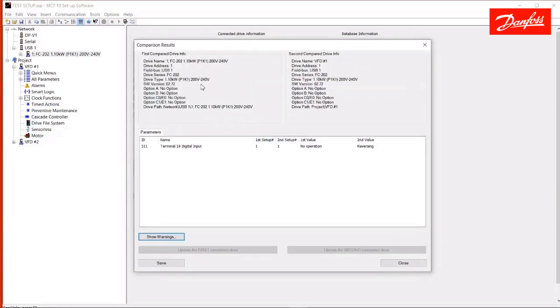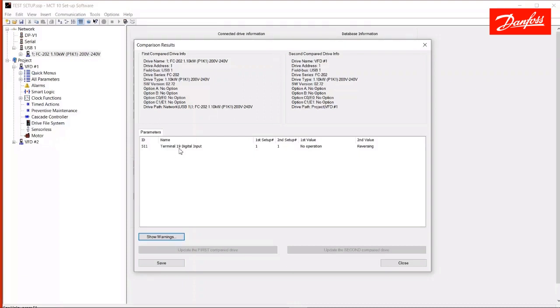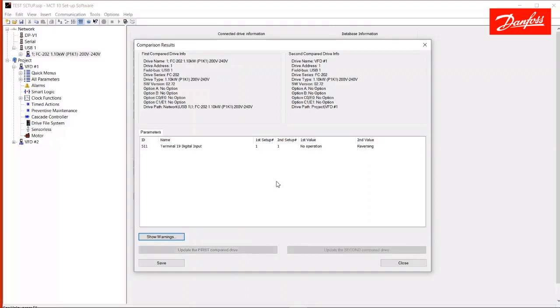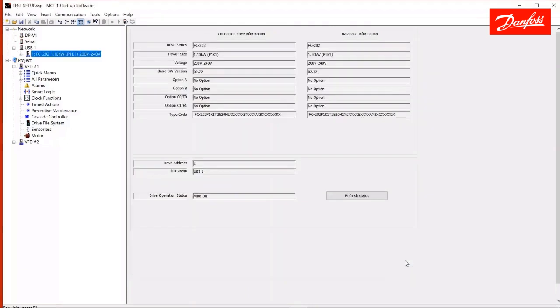Okay, so the first compared drive, which was the live drive and the USB, we compared to drive number two, the project drive, VFD number one, that I made the one change to, which was changing terminal 19 to the value reversing. So, it came up with the one parameter that was different between the two drives. That can be a useful function when troubleshooting.